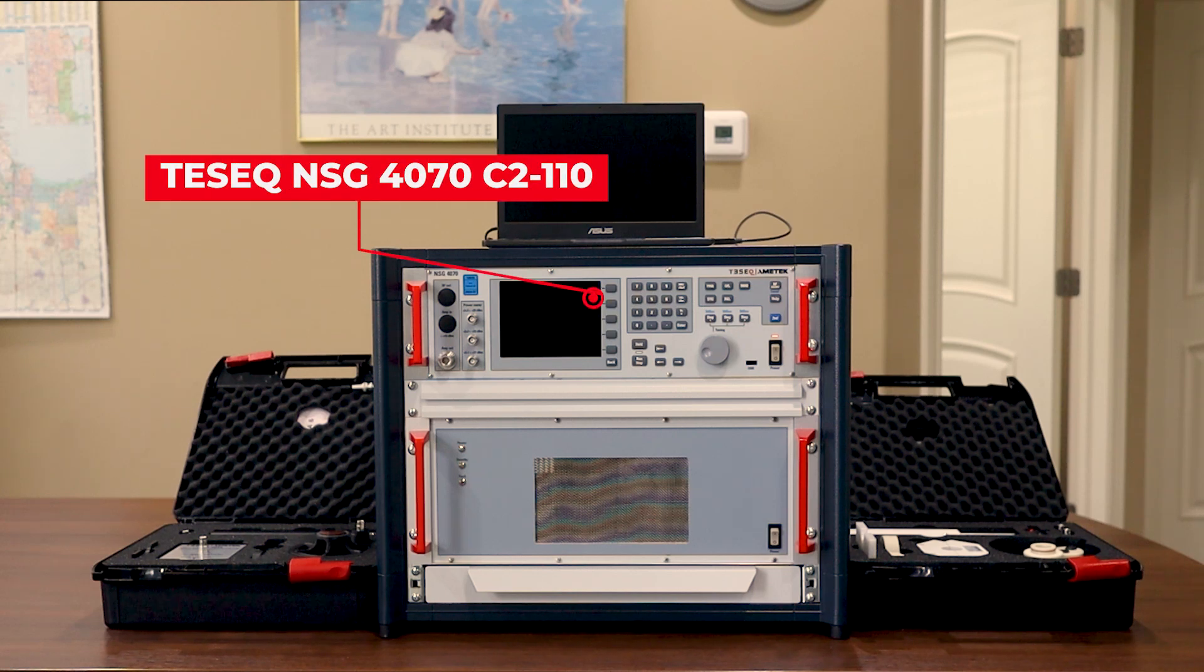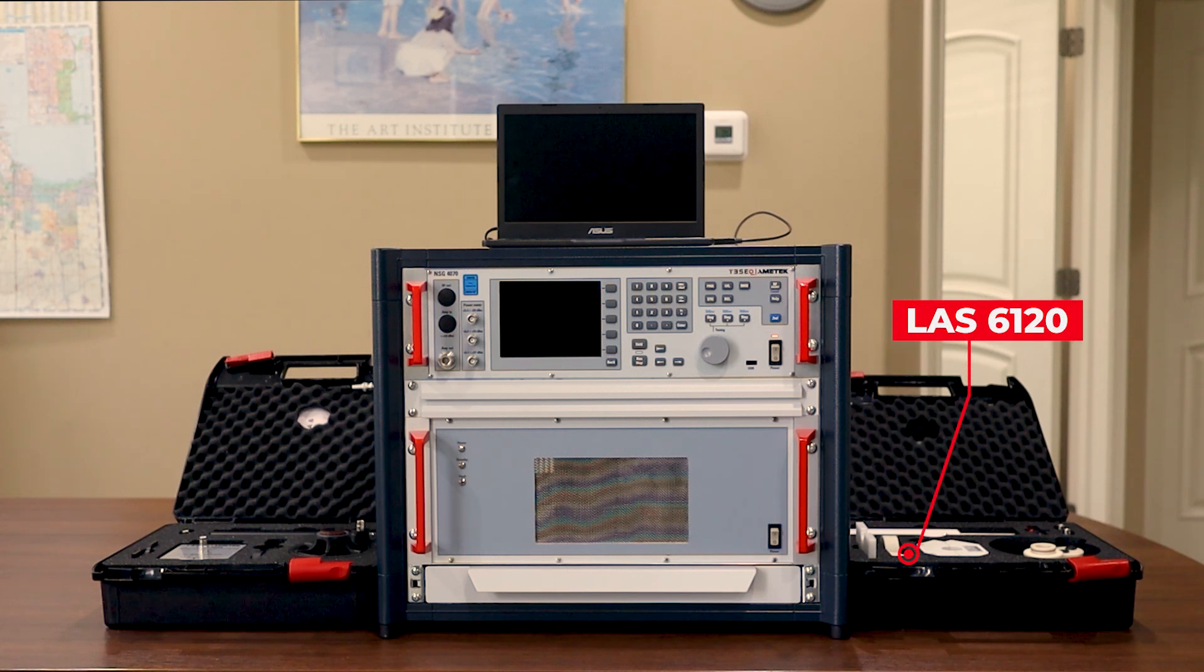During today's video we're going to be using the TESEQ NSG4070C2-110 test system with the TESEQ LAS6120 and 6100 antenna kits. The NSG4070C2-110 can be used for this test and has a built-in amplifier meeting the test level requirements. In many situations however, the NSG4070C-LFCP is also used. We're going to be using the ICD.control software for today's video, which we'll take a closer look at later.